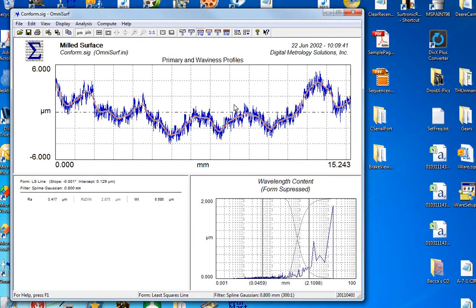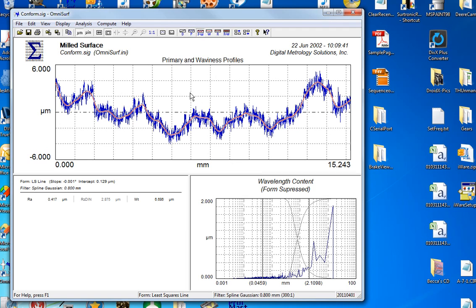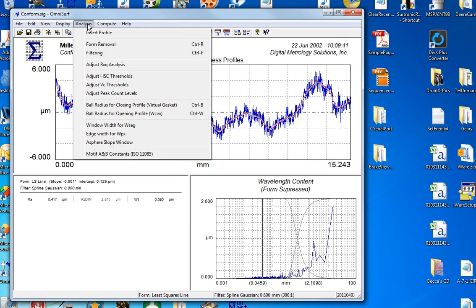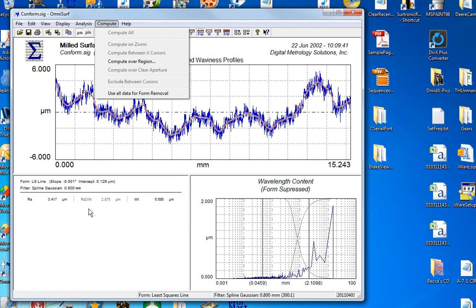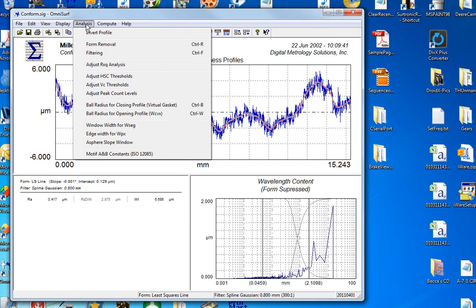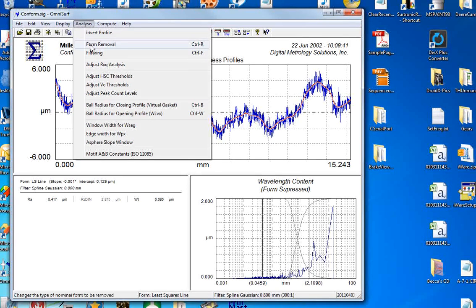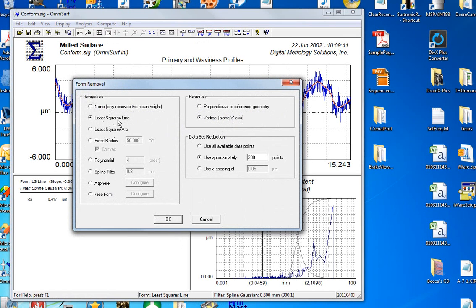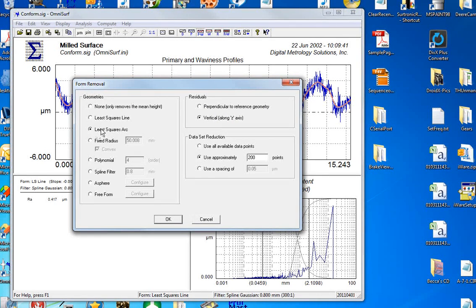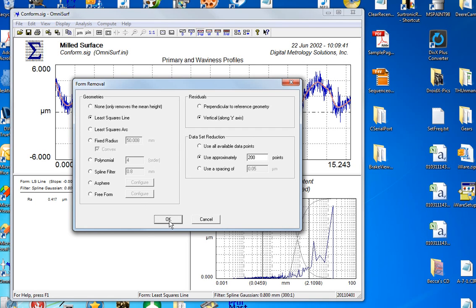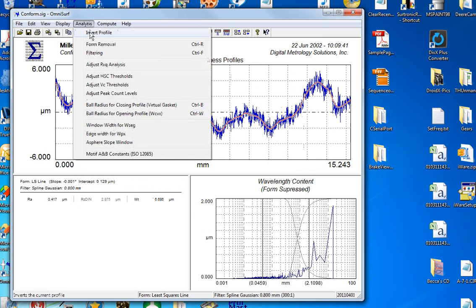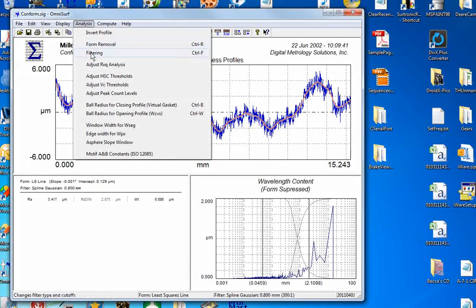Last thing I'd like to talk about is the selection of your settings. One thing that people don't often know is how do I choose my filtering and my form removal? The analysis menu is where all of the numbers get changed. Anything in the analysis menu is going to change a calculation. So on the analysis menu we need to check two things: form removal. In this case, the surface was a flat surface. I know that this is a flat surface, so I'm going to use a least squares line as my reference. If you're measuring on an arc or over a curve or some equation you can choose these other options, but this is a flat surface so I'm using a least squares line.